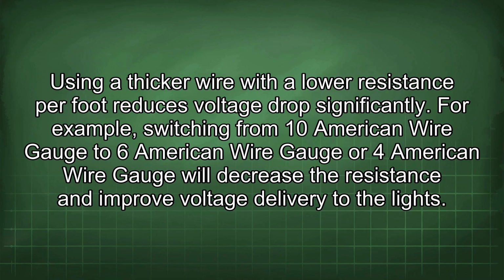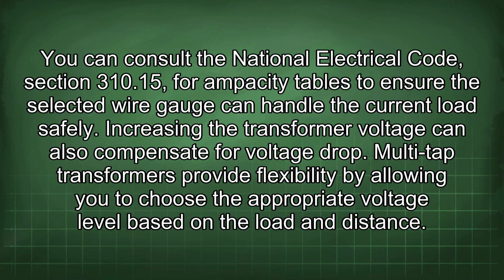Using a thicker wire with a lower resistance per foot reduces voltage drop significantly. For example, switching from 10 American wire gauge to 6 American wire gauge or 4 American wire gauge will decrease the resistance and improve voltage delivery to the lights. You can consult the National Electrical Code, section 310.15, for ampacity tables to ensure the selected wire gauge can handle the current load safely. Increasing the transformer voltage can also compensate for voltage drop.